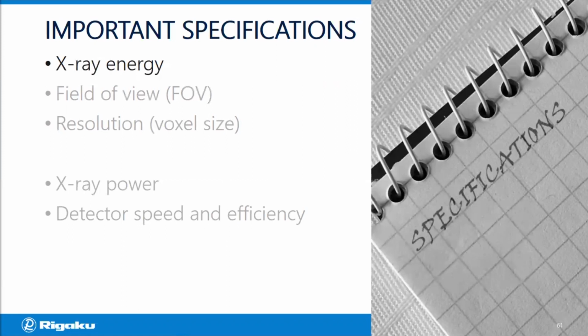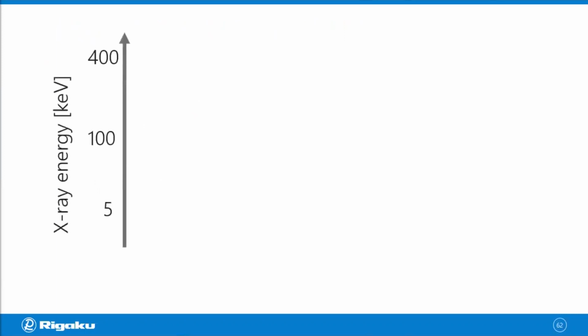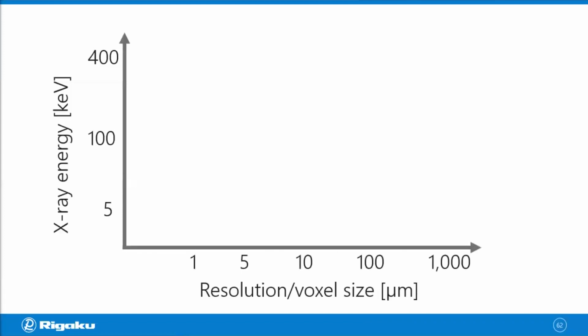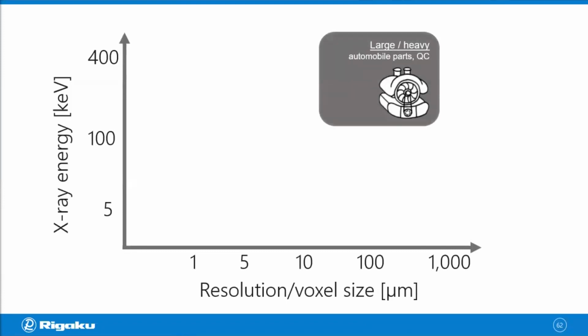You can roughly categorize X-ray CT scanners in three groups. And those three groups have different X-ray energy they cover. So if you put the Y-axis as your X-ray energy, then you put the X-axis as a resolution, one category would be positioned here. So if you want to see large and heavy samples, like engine parts, then you would need high energy, somewhere from 200 to 450 keV. But because you're looking at a large sample, you probably don't need high resolution. So this category covers high energy, not so high resolution voxel size range.